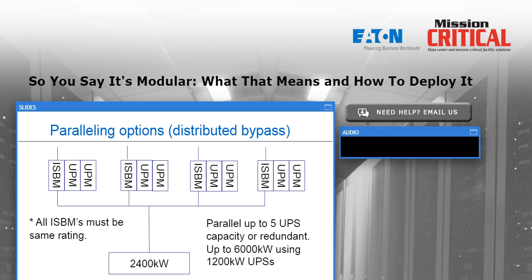The other thing that we have to think about is the I/O module, or the thing we kept calling the SBM, or system bypass module. That module is a single piece of the UPS system that contains things like input breakers, bus bars, terminations for cabling, the static switch, for example, and all of those things are size sensitive. So on the one hand, my I/O module has to be sized for the maximum possible that UPS could ever be. But the expensive and space-intensive power modules can be added on an as-needed basis until I hit the point where my I/O module can't handle that much current. At that point, I have to go to a bigger UPS.